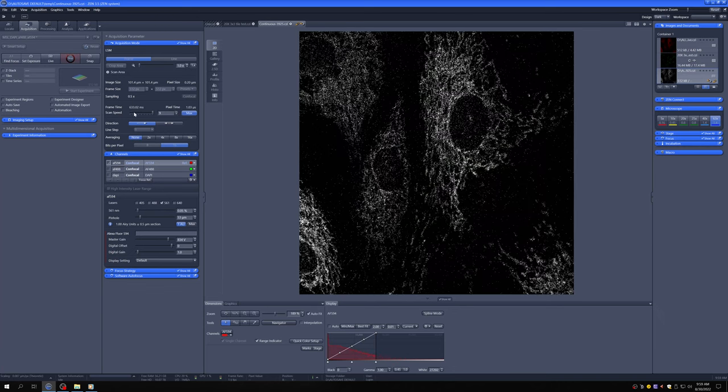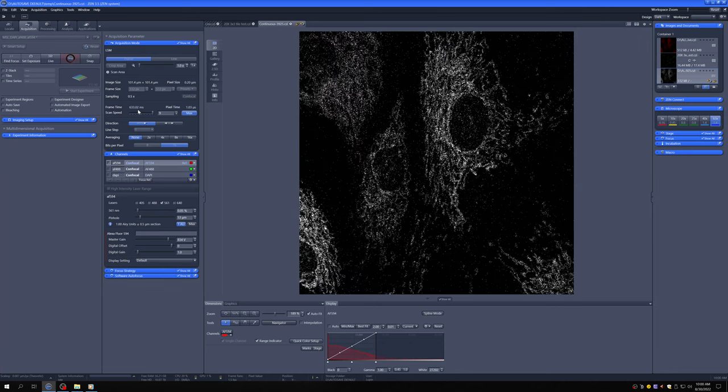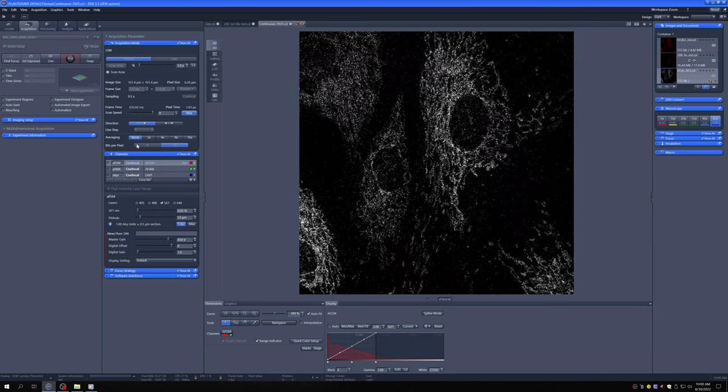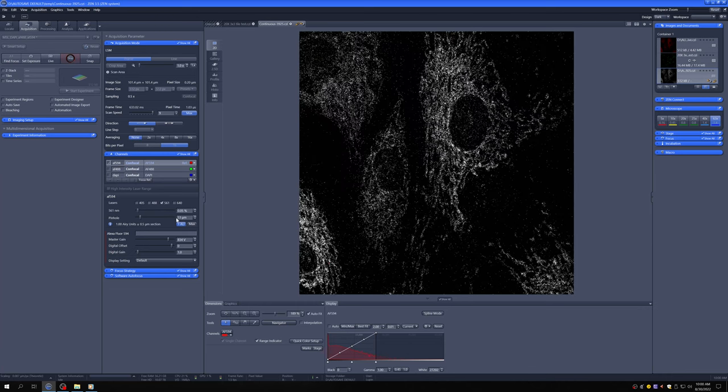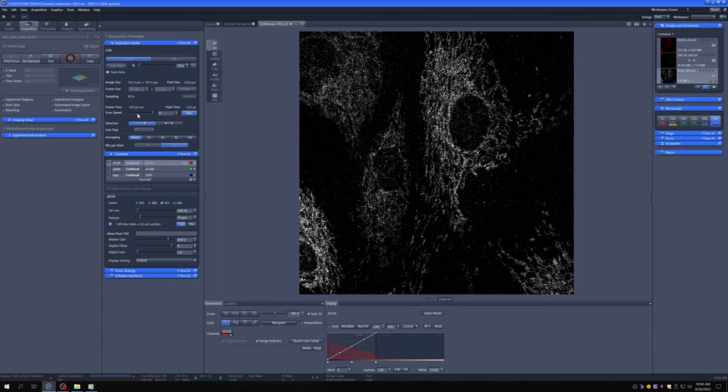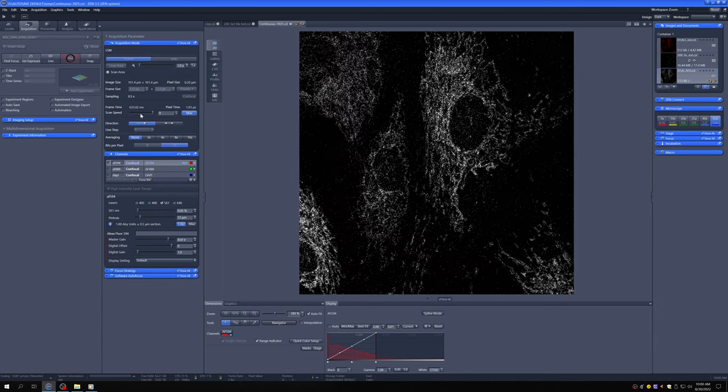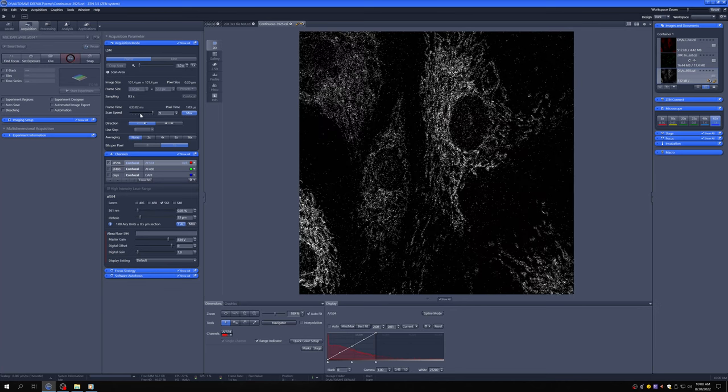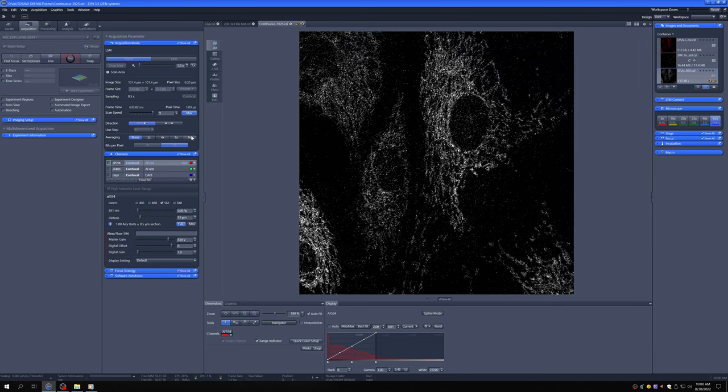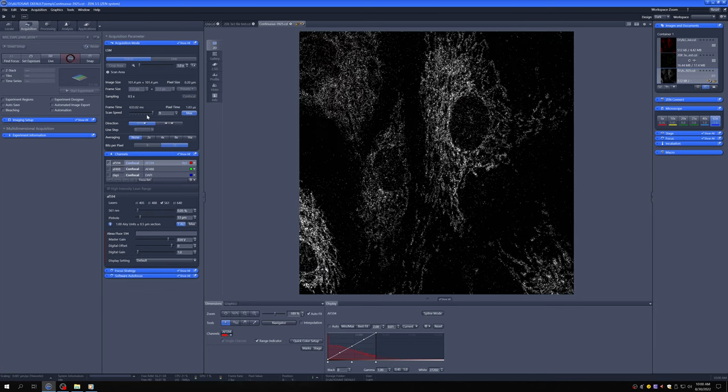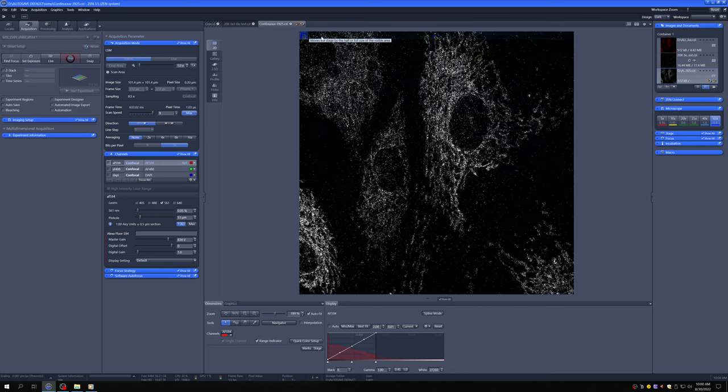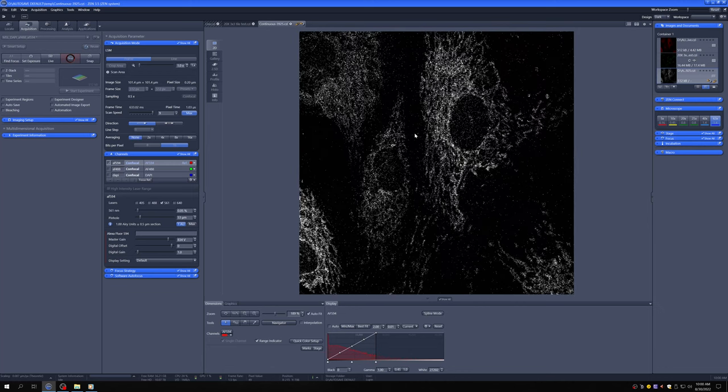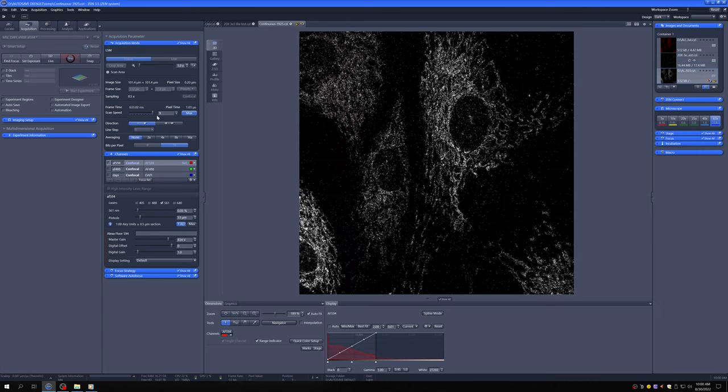So what about scan speed versus averaging? Both of these take longer and bleach more than not doing them. We've already discussed how increasing the laser power bleaches more but doesn't have a time penalty. So would we ever use adjustments to scan speed? And the answer is usually not. Usually it's best to maximize the scan speed. The reason is scan speed for the same amount investment of time as the averaging, it usually bleaches a little bit more. So it's worse for the sample to have it move the laser slowly across than to go back and forth over the sample several times. That's just kind of an empirical thing that we've observed. So usually you just want to max it out.